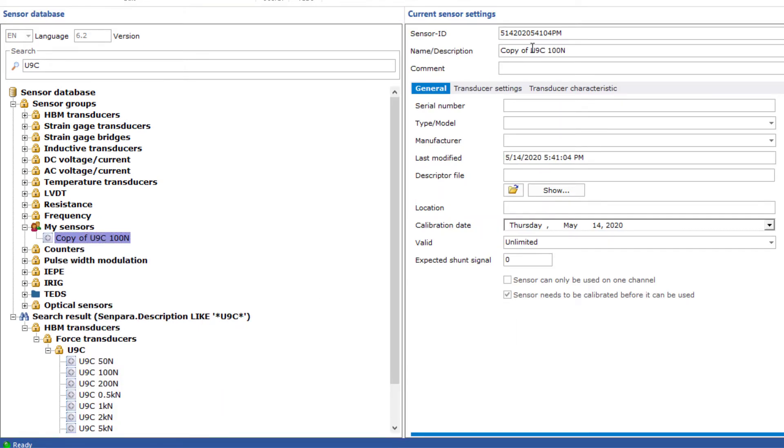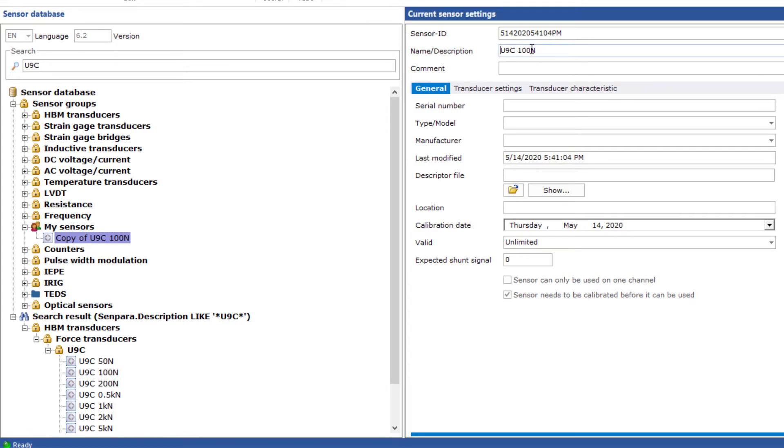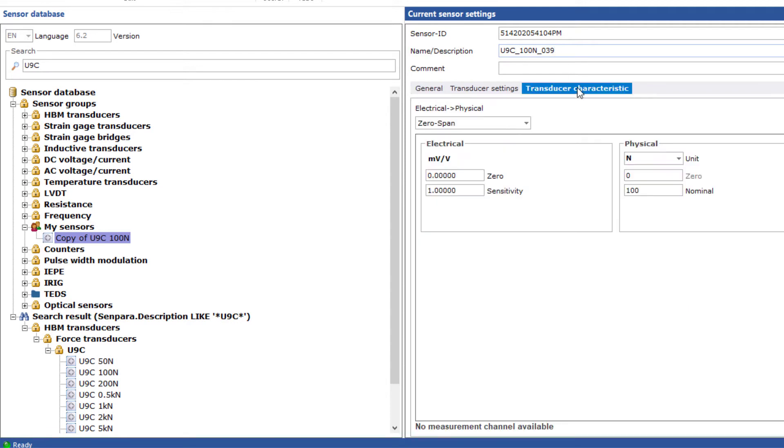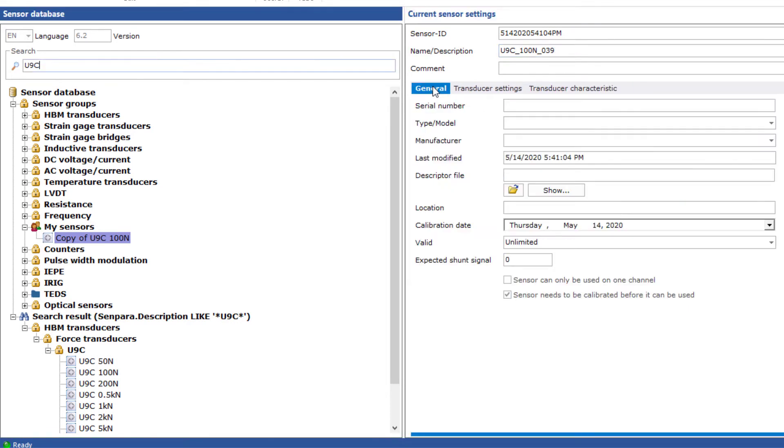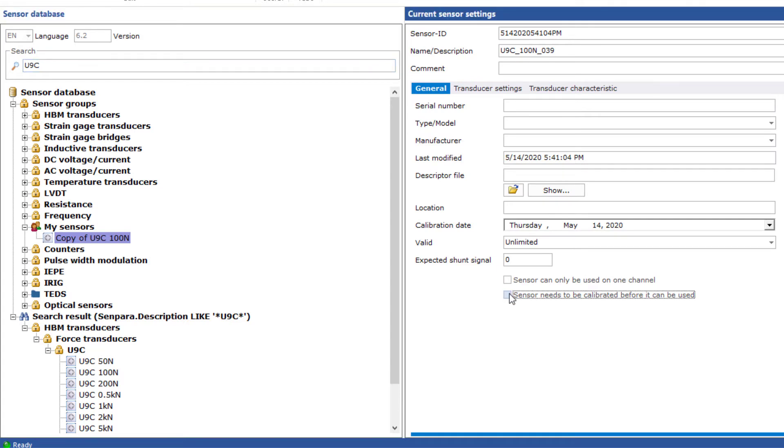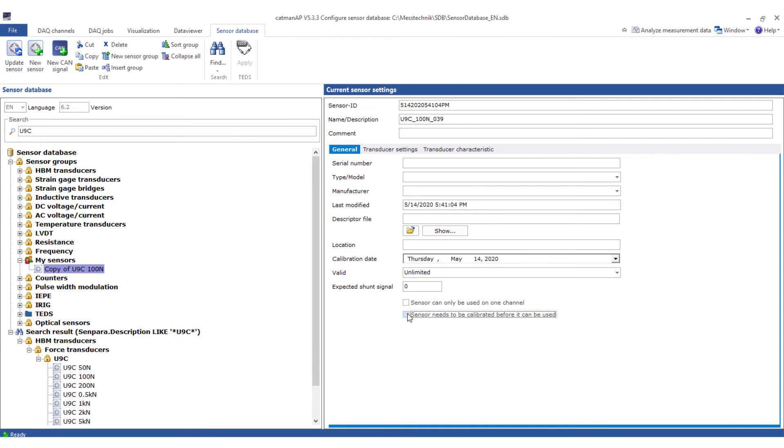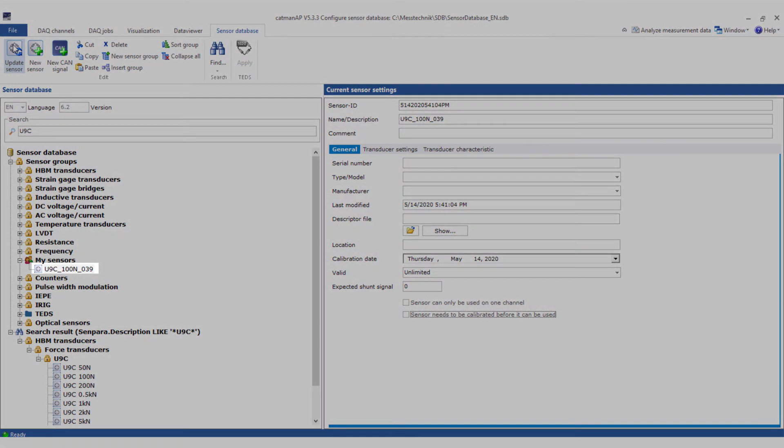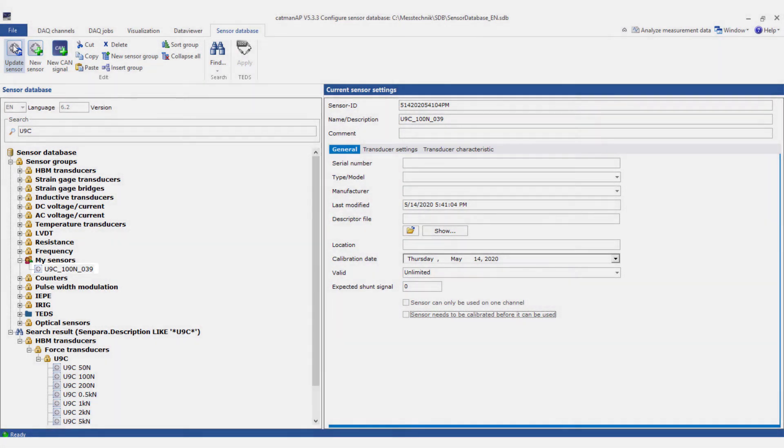First I'll change the name. I'll append the last three digits of the serial number to the name, and then enter our sensor's sensitivity value. Finally, I'll remove this check mark so that I won't be prompted to enter the password in the future. The input of further parameters like comment or calibration date is optional. With Update Sensor all settings are applied. Now you have created your first own sensor.